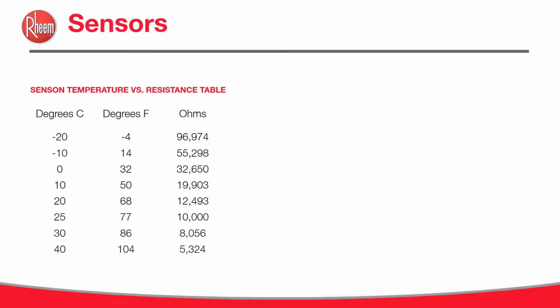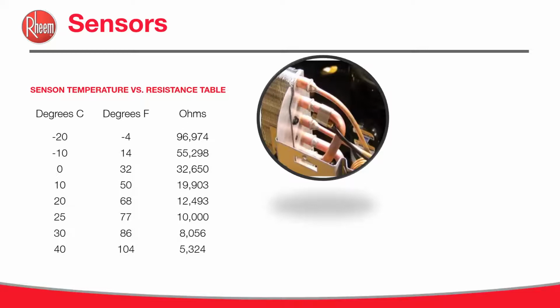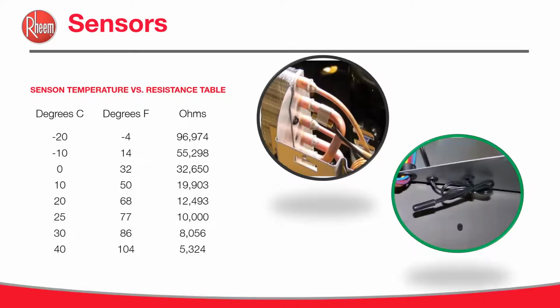So now let's look at the sensors. The control board uses two sensors: a coil sensor, which reads the outdoor temperature in the coil, and an outdoor ambient temperature sensor. Both these sensors assist in the defrost process. On your higher end units, there are 4 sensors in the outdoor unit. There's a sump sensor on the bottom of your compressor, there's a coil sensor, there are more sensors. So again, it's more complicated than it is on a simple system.